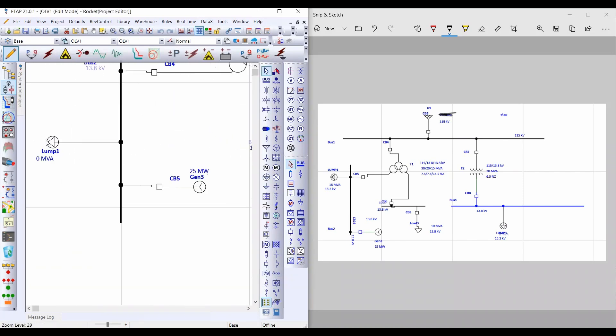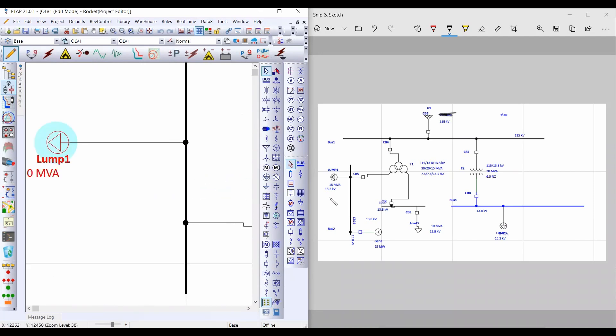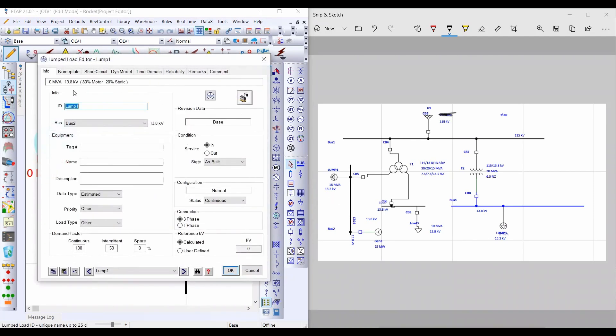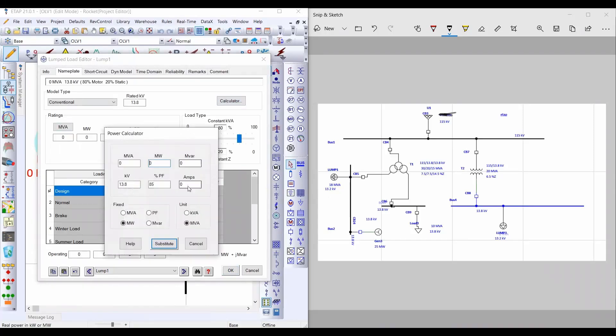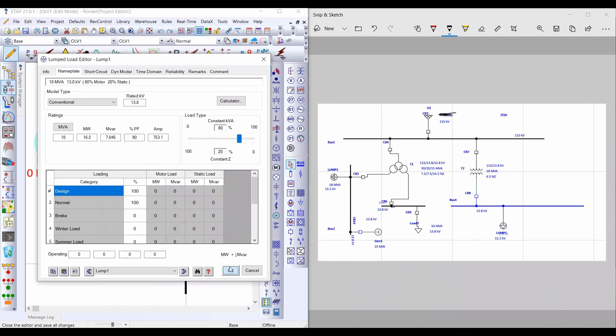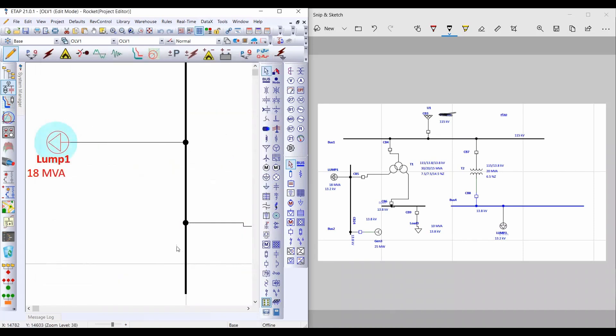The value of the second lumped load is 18 MVA. Double left-click on it, then from the Calculator select Fixed MVA. Insert 18 MVA and set the power factor to 0.90, then click Substitute.